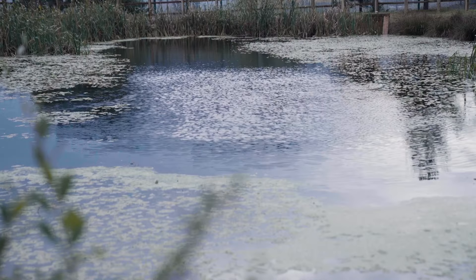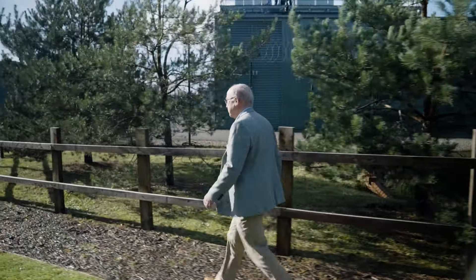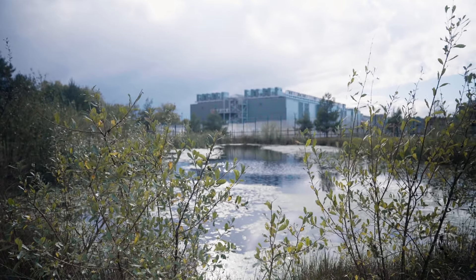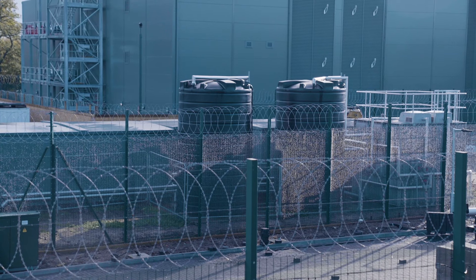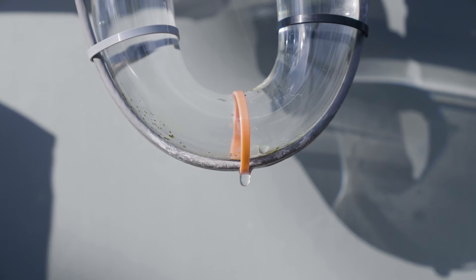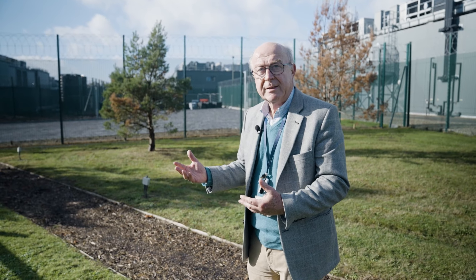Direct fresh air uses a lot of water, so what we did was put in rainwater harvesting systems. This collects rainwater from A102, A101, and most of the campus, which then goes to a treatment plant — you can see the big green tanks. That treatment plant takes the rainwater, filters it, puts it through a UV process, and then depending on the salt content, it can either go straight into our evaporative coolers or go through an RO plant to get the salts out.